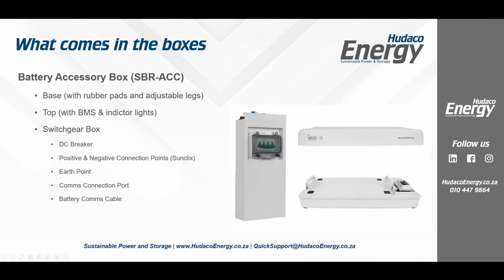The other thing that comes is the top section. Now, in the top section, you've got your battery management system built into it. So it's included in the top. You've also got your power on-off button and your charging indicator. So these are your lights. These are blue when the system is on. If you've got an error, this will go red. And your charging bar, as you're charging, it'll flash up, or if you're discharging, it'll flash down. And then when it's not charging or discharging, you will see the number of bars will show you your percentage. There's 10 here, so 100%, all 10 would be lit, 50%, 5 of the 10 would be lit.